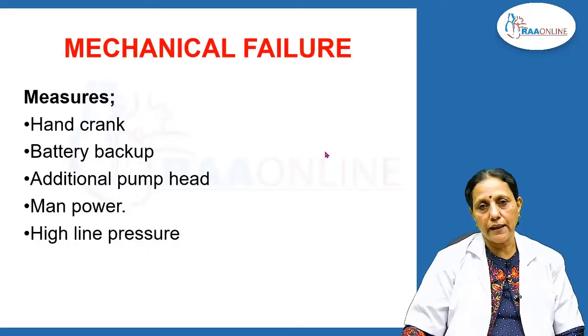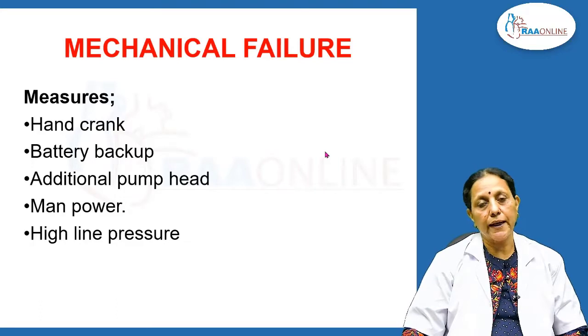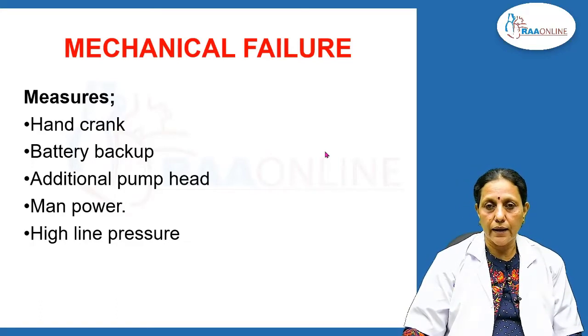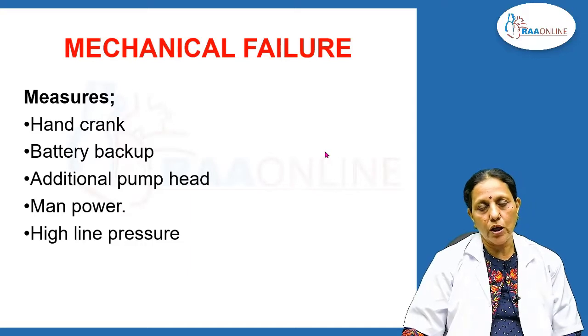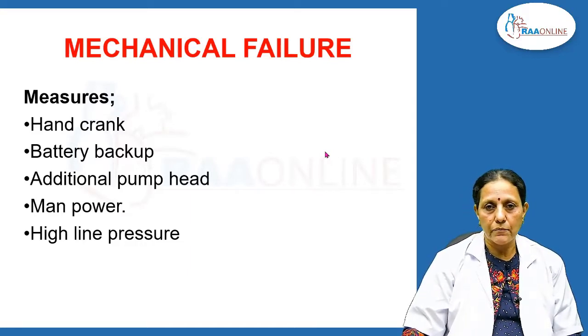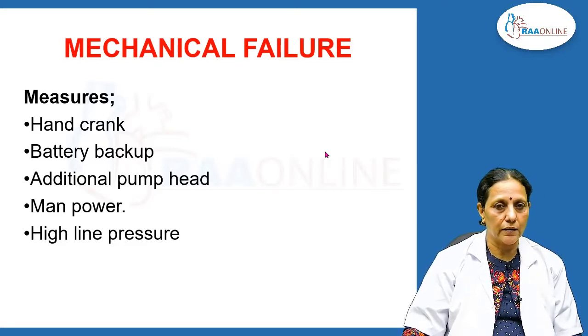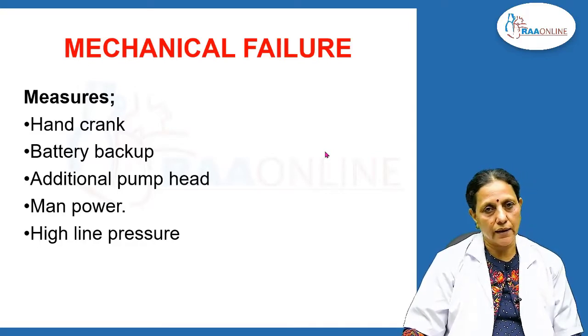Now, mechanical failure, as I told you, it can be on the pump side. So, what do we do? Suppose the pump stops and there is no electrical supply. The pump has to run. So, you can use a hand crank, which is part of every heart-lung machine. This is inserted inside the pump and manually we can run the pump. That is the first method.